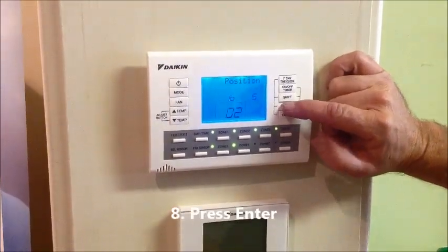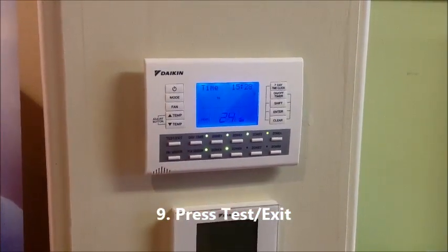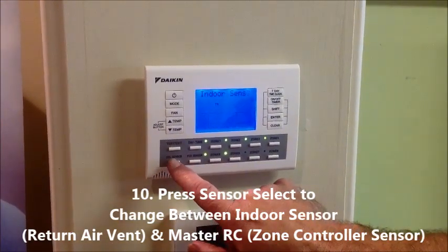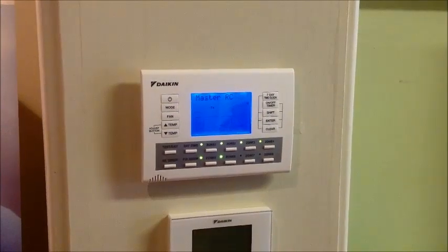Then we press enter and that should be logged in now. Press test once to get out of it, back to the normal screen. Then when we go to our sensor select, the first one is the indoor sensor and we should have master in there as well. We can press sensor select and that's now reading from the master sensor.